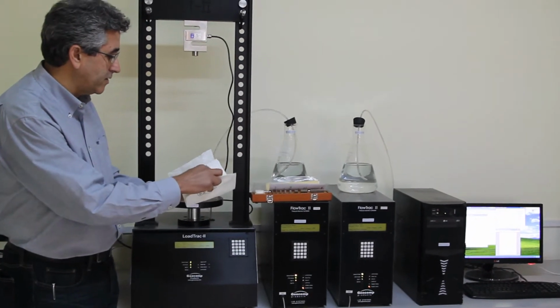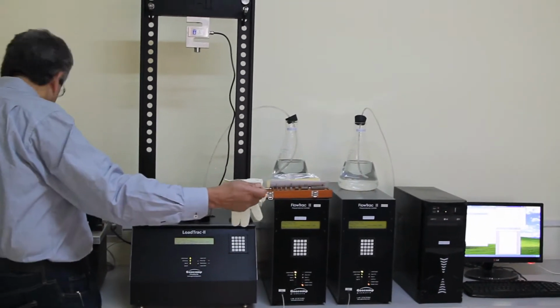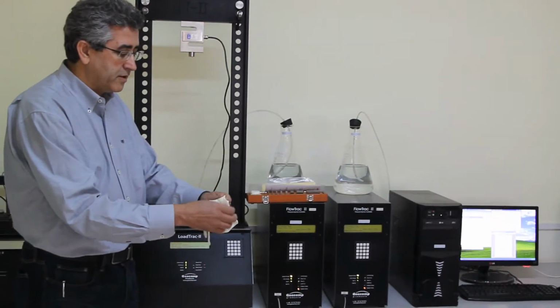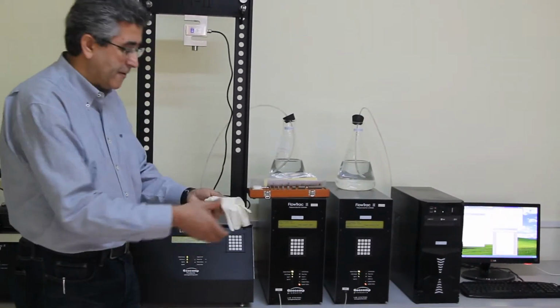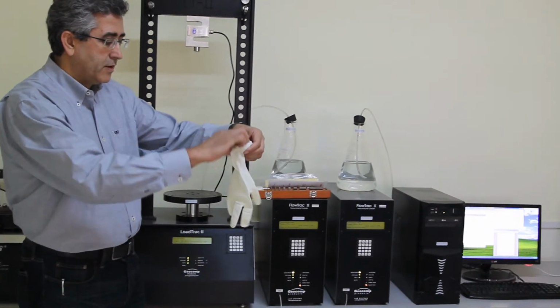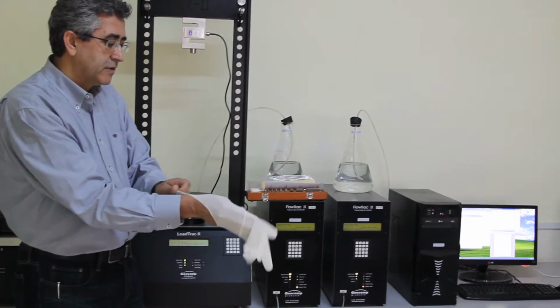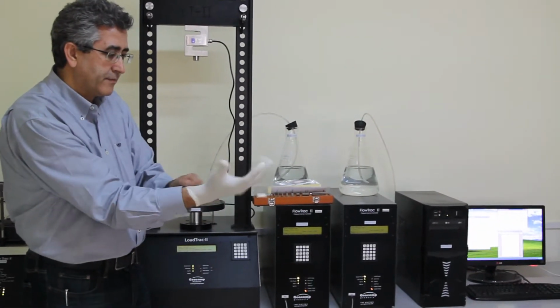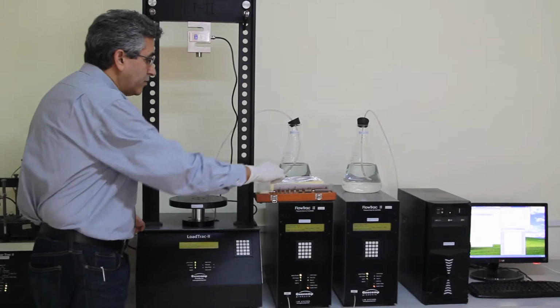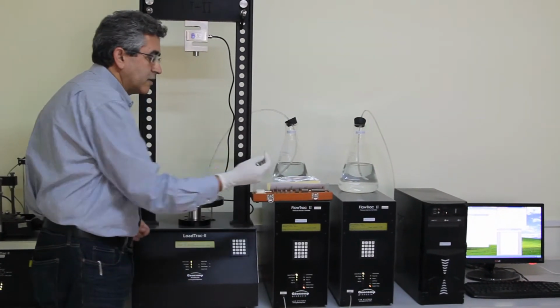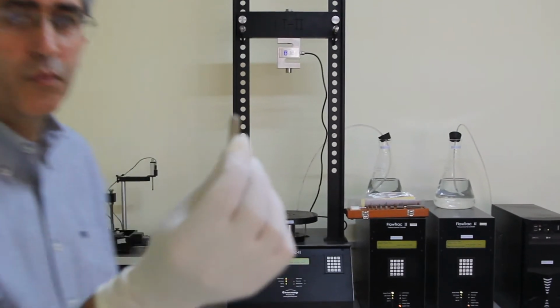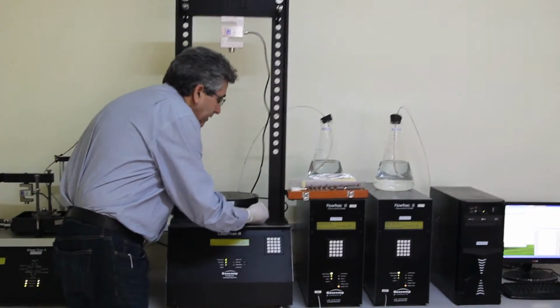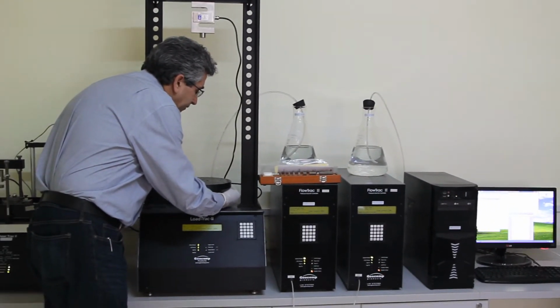And so the next thing I'm going to do is handle these gauge blocks, and it's recommended that you use rubber gloves. So I'm going to put on my rubber gloves so I can handle my gauge blocks. Now I'm going to take my first gauge block, which corresponds to 0.0625, and it's written on it. Just make sure that you insert it the correct way, which is the smooth side here. So I'm going to go underneath my platen and insert my first gauge block.